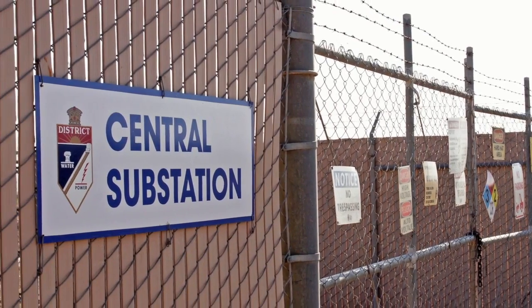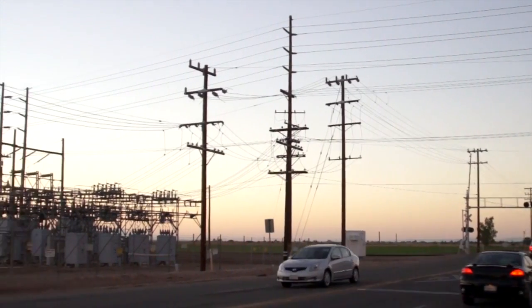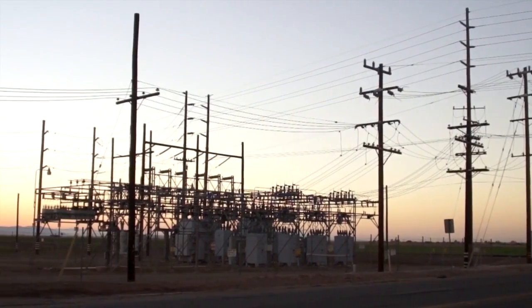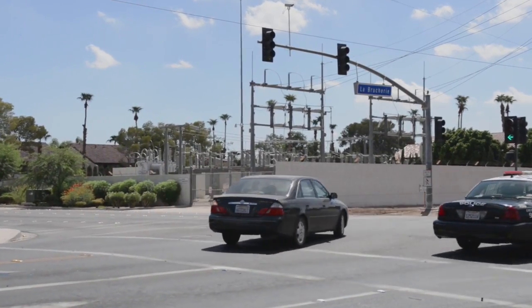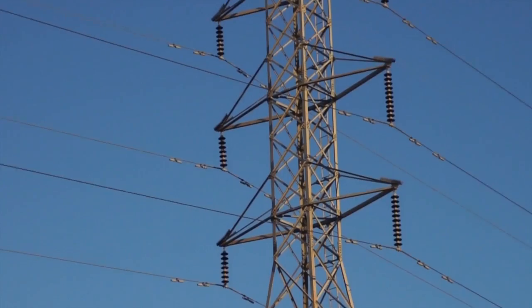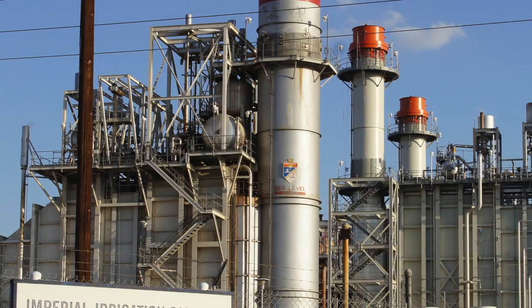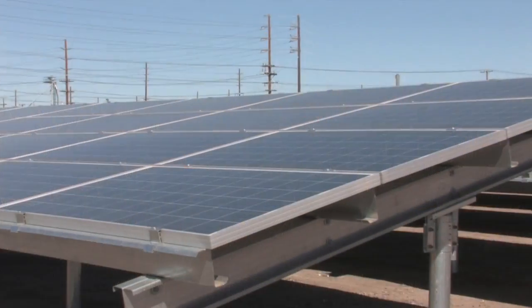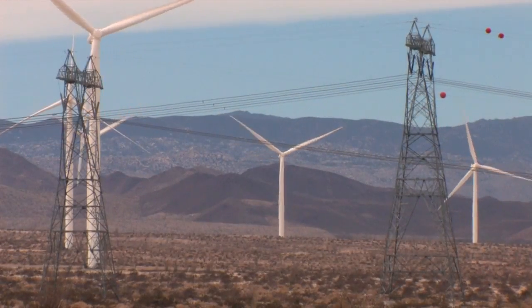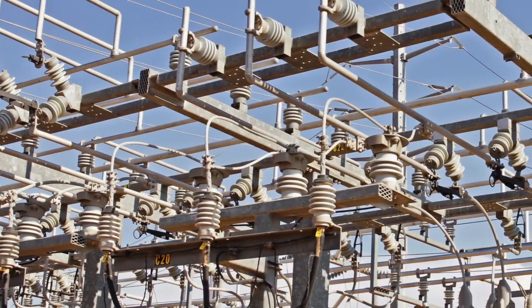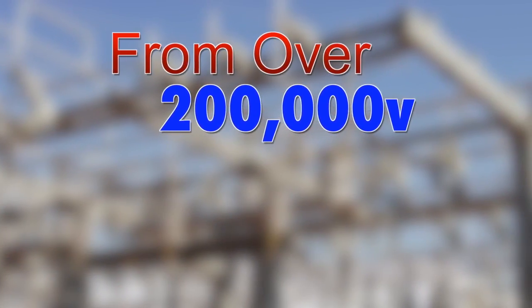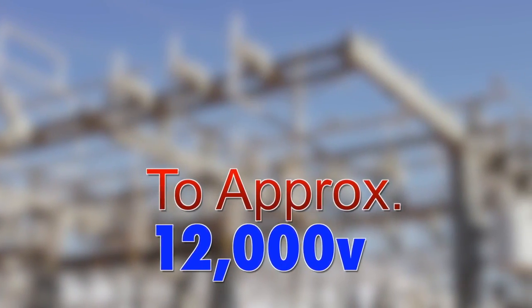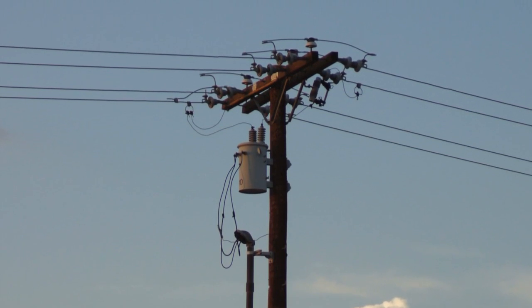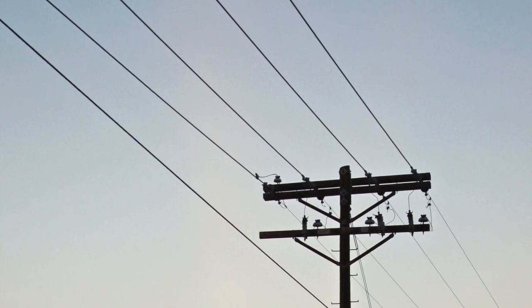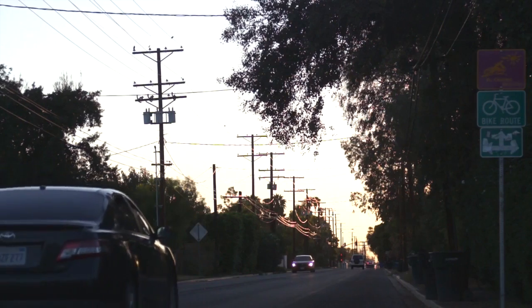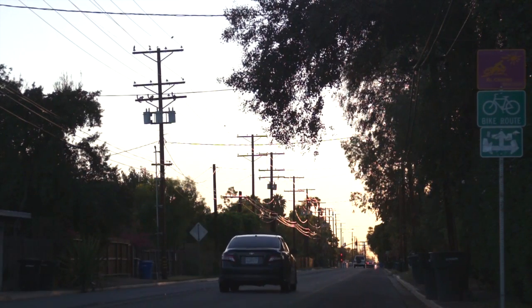First, let's talk about substations. Substations are the hub for energy to be distributed to homes or businesses in the surrounding areas. The substation receives energy from transmission lines, which are fed by some type of energy generation, either traditional or renewable resources. Substations take transmission voltages of well over 200,000 volts and step the energy down to approximately 12,000 volts on a three-phase system, meaning there are three different conductors carrying alternating current into neighborhoods. The electricity is then distributed to areas where the power is needed.